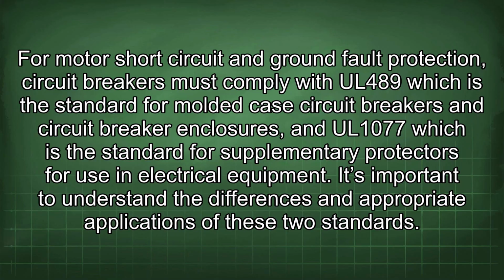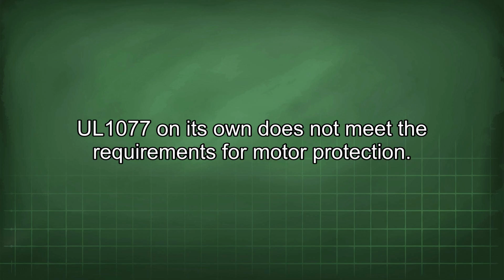For motor short circuit and ground fault protection, circuit breakers must comply with UL 489, which is the standard for molded case circuit breakers and circuit breaker enclosures, and UL 1077, which is the standard for supplementary protectors for use in electrical equipment. It's important to understand the differences and appropriate applications of these two standards. UL 1077 on its own does not meet the requirements for motor protection.